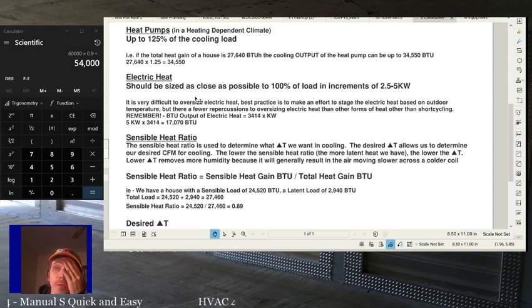But there are fewer repercussions to oversizing electric heat. It's pretty hard to put yourself in a situation where you way oversize the electric heat. In general, you should err on the side of putting an extra 5 kW in there. It's not hard to just delete a strip of electric heat if you need to. So the biggest factor, and I didn't note this here, that's going to limit how big of an electric heat kit you can put in is going to be the size of the wire going to the kit, right?